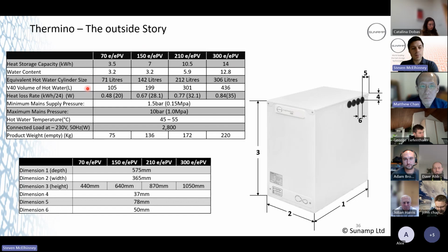So the V40, what that is, part of our system components, we'll strongly advise to fit a thermostatic blending valve on the outlet pipe, because once that battery is up to temperature, you can have up to 80 degrees coming out the draw-off pipe initially. So you've got to blend that down. It's an anti-scald device primarily, but secondly, if you set that TMV to 40 degrees on the outlet, you can increase the capacity of your heat battery. Because essentially, if you set it to 40, you're restricting the heat that's leaving the heat battery and blending it down, adding a bit more cold water to the outlet. So that's how you can increase your capacity there.